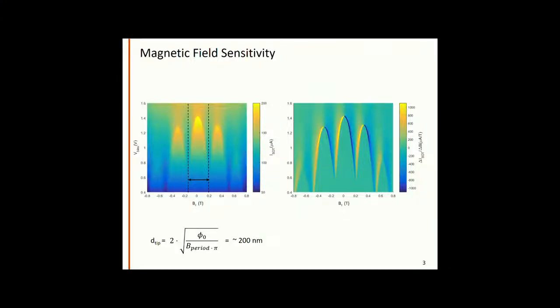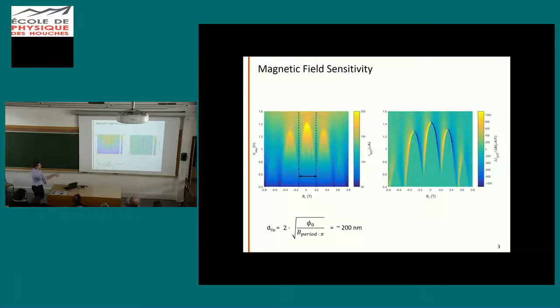So basically, you're right. This is only a sensitive sensor at these particular fields. Now, the sensitivity is optimized here, but of course you can see you have some sensitivity all along these lines, and basically you have certain blind spots in the field that you cannot measure. Now that's for our sensor with two Josephson junctions. That turns out to be, we have enough working points that it doesn't really matter in most cases.